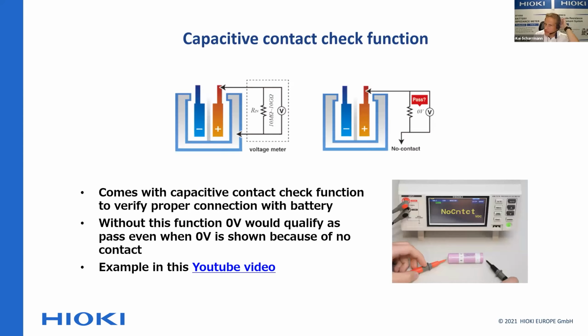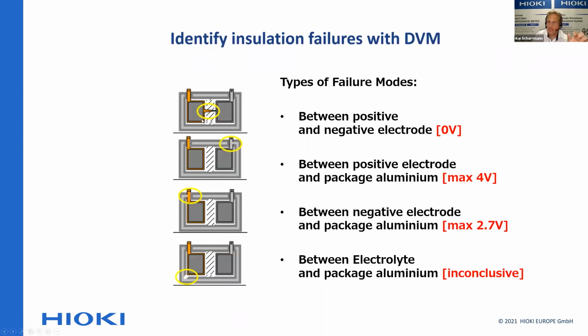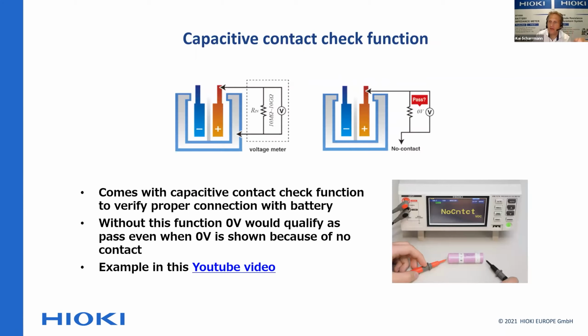One crucial thing is that you need a contact check function, because you need to be sure that when you make these measurements, you actually have contact between, for example at the very top picture, the positive and negative electrode. If you have no contact, a normal digital multimeter would show 0 volts, because no contact in a multimeter always reads 0 volts.